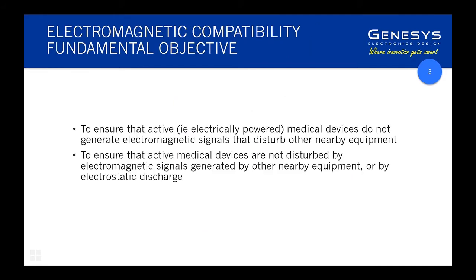Before you start, can I ask — among active medical devices today, would virtually all have some sort of connectivity? It's not a one-to-one relationship — you can still have electromagnetic issues when there's no connectivity, correct? Absolutely — any electrical device has EMC obligations, and that applies to commercial devices as well as medical. The radio brings additional requirements because of the radio transmission aspects.